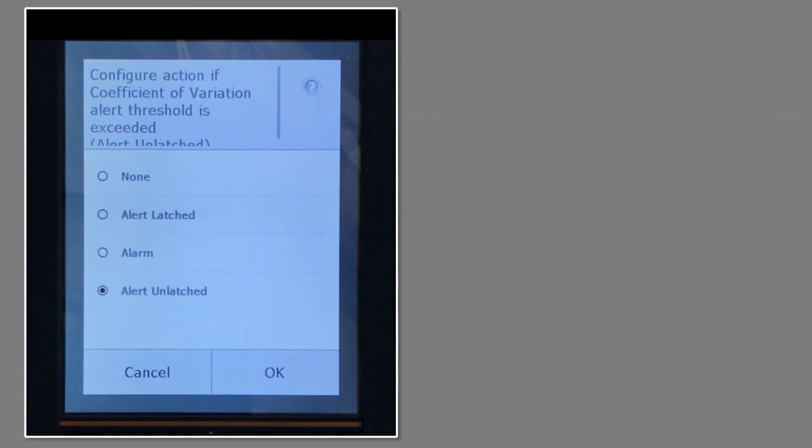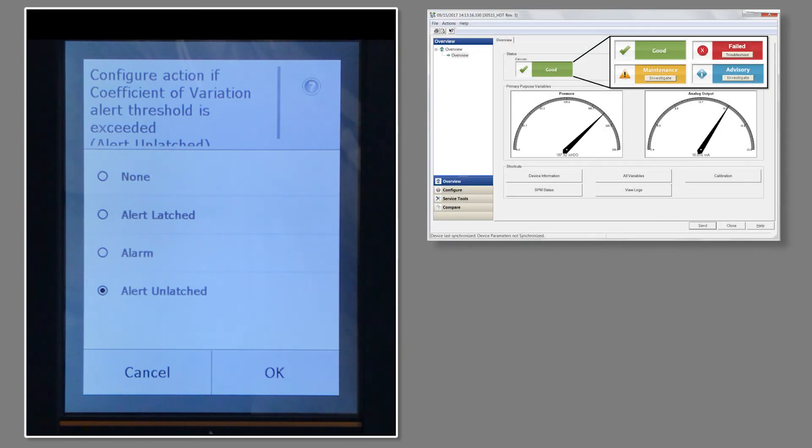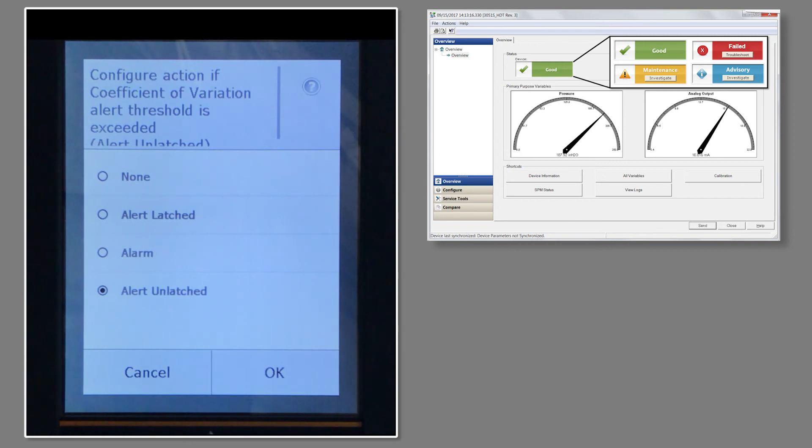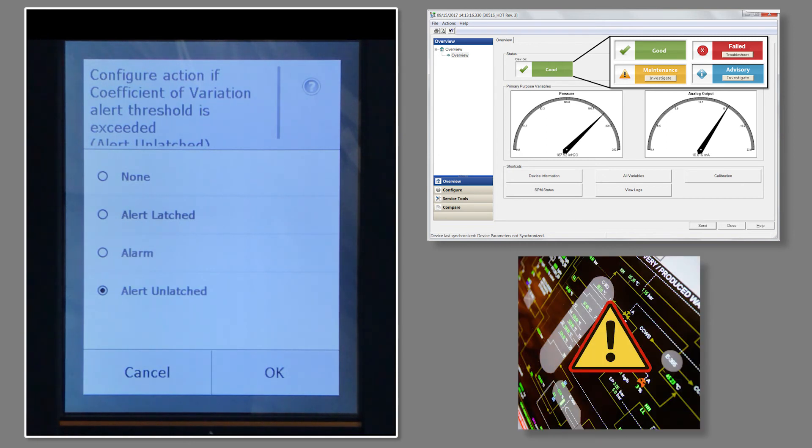To finish, set the action for when the sensitivity threshold is crossed and an abnormality is detected. An unlatched alert will generate a notification and clear automatically when the process returns to normal, whereas a latched alert will require a manual reset to clear. Alarm will drive the milliamp output to an alarm state. I'll be selecting alert unlatched.